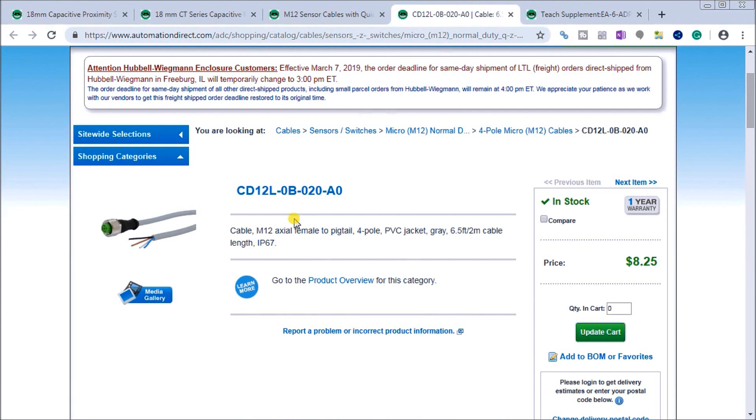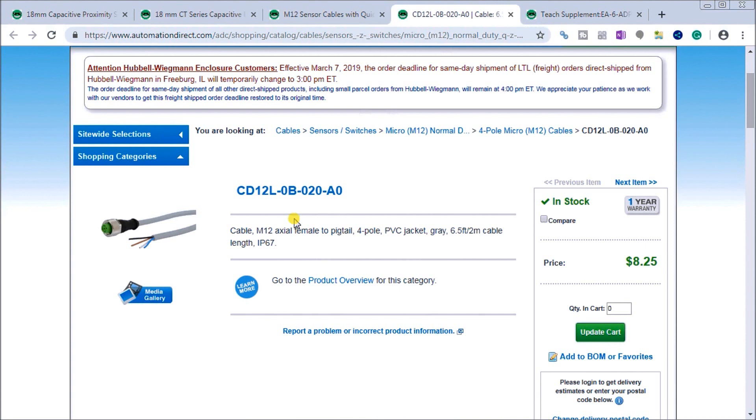A capacitive proxy sensor will detect ferrous and non-ferrous objects. The sensor works by oscillating the charge on plates in the sensor. When an object is placed in front of the surface the amount of current flow is detected, it's capacitance. The permittivity will determine the distance that the object can be detected. So even though we have a 12 millimeter sensing range that may change depending on the object that we're actually detecting.